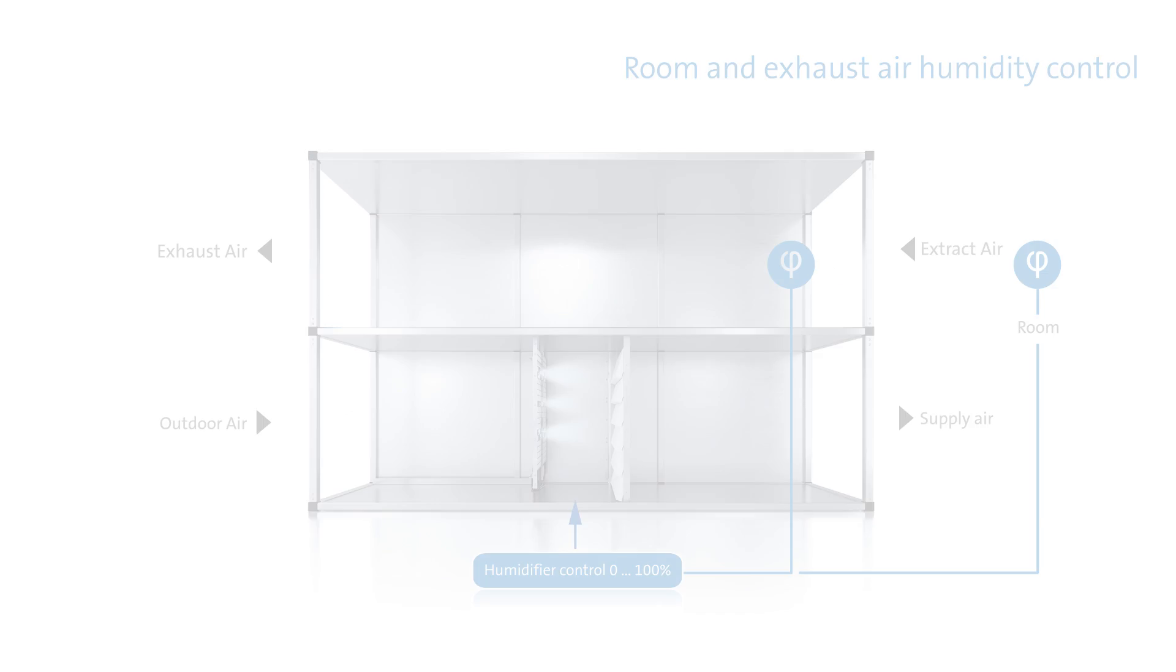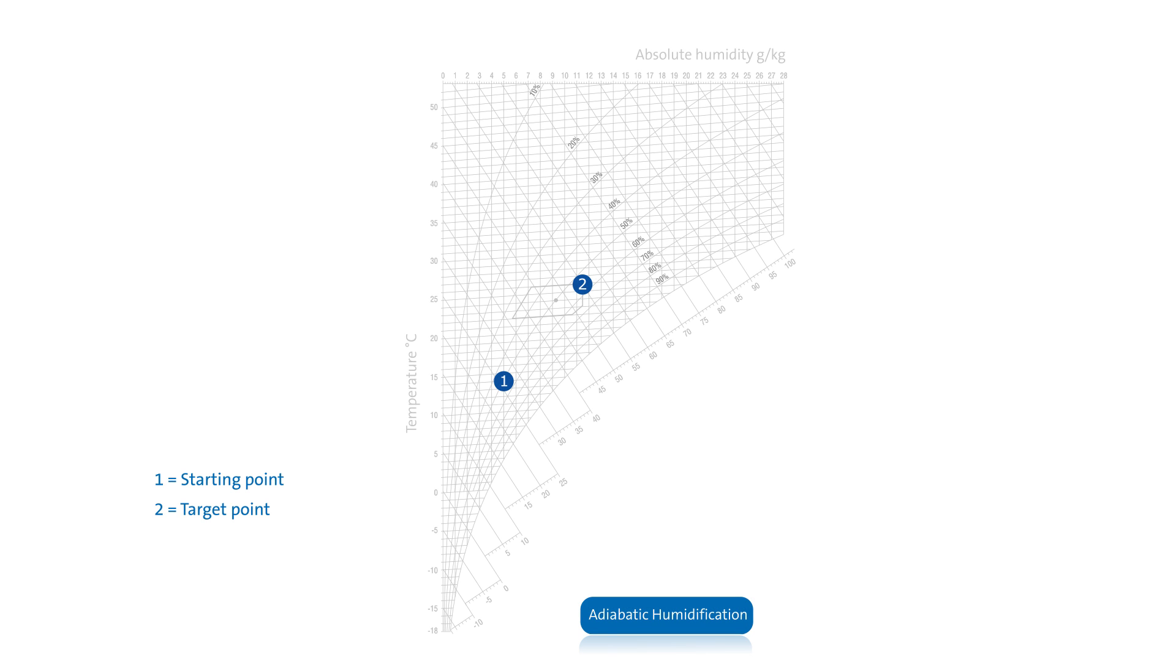The control system for an adiabatic humidifier must also take the adiabatic temperature drop into consideration. In this case, an enthalpy or a dew point control system are appropriate choices to provide control.